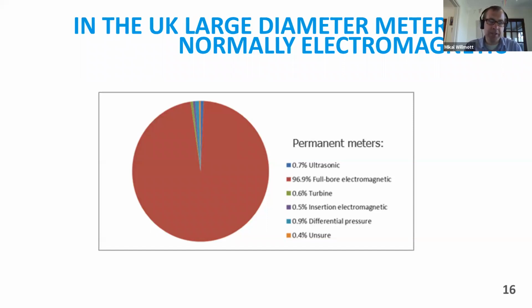It's also worth saying that over the last few years, clamp-on ultrasonic metering has become more popular in the UK. And the reason is, 30 years ago, if we wanted to install a meter in the UK, and Alan Thomas, who's on the call, did lots of this for Severn Trent 30 years ago, we'd write a really nice letter to the customer saying, we're going to turn off your water for a few hours during the night because we want to install a flow meter.